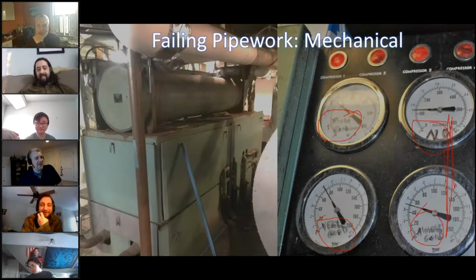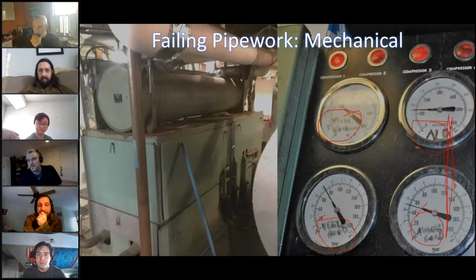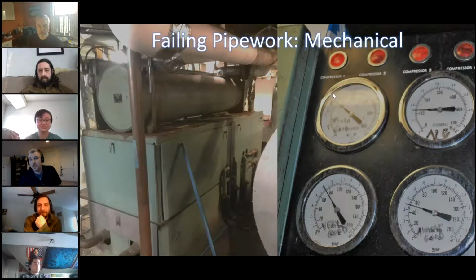So when you have this, it should be keeping the water temperature down to, say, 44 degrees on the chiller. It was in the 50s. It just couldn't maintain the water temperature to maintain the space conditions. So the makeup air unit would be turned off because it couldn't maintain the air coming in. It was able to maintain the temperature, but not the humidity in the building. So the sensible load would be taken care of, but not the actual latent load. It'd be 70, 72 degrees in there, but very humid. All right, so it's also a mechanical issue going on inside here. So trick question, both.